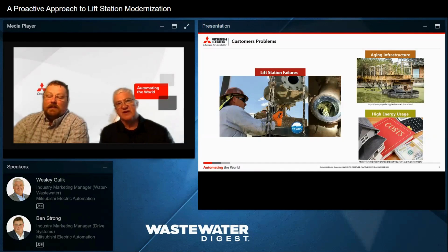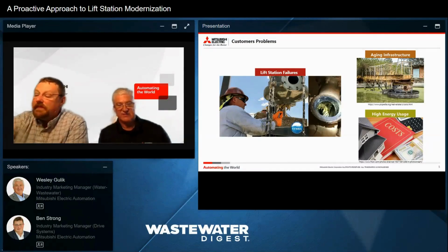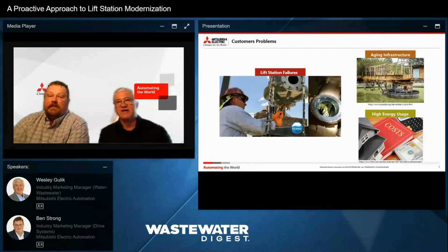The other thing with lift stations, which we'll be covering, is the mechanical wear. These pumps are approaching 40, 50 years and approaching end of life. So we need to start paying closer attention to it, as well as the electrical panel. And that's our second point, the aging infrastructure, approaching 50 years. And we need to be proactive and start making changes as we move forward. And then the high energy costs. So how do we go about trying to maintain that energy cost? And it's simply taking advantage of today's technology. So I'll kind of reference back, while this is fresh in my mind, with the Hydraulic Institute. Here you can have energy savings using controls, the VFD as opposed to soft start or across the line. But there's also tremendous savings that can be realized using proper pumps. And that's what one of the earlier sessions this morning was about, efficiencies, specifically using proper pumps.